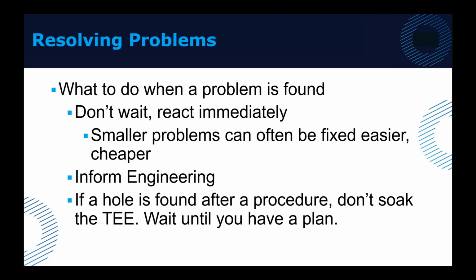That would usually take, we tell hospitals to call us. Because what we want to do is make sure we're setting up with our facility in Tulsa that they know this probe is coming. What we don't want you to do is do this on a Friday, and then send that probe to us. It's going to be the weekend, it's going to get there on Monday. We still have ISO policies that say that probe sits there for 24 hours.